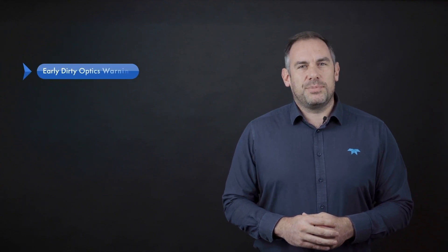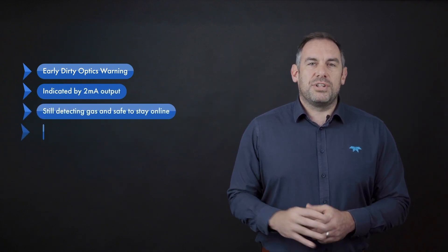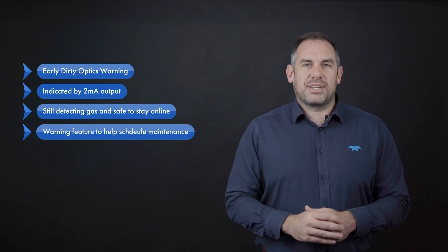To summarize, when the device goes into the early dirty optics warning state and outputs 2 milliamps, the device is still detecting. What it means is you should schedule in either a device swap out or a lens clean into your maintenance schedule.